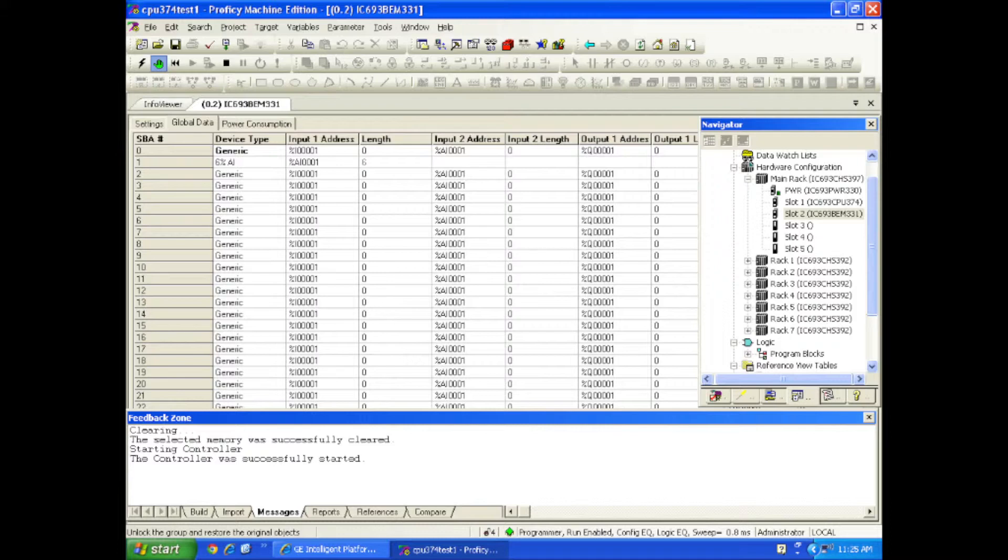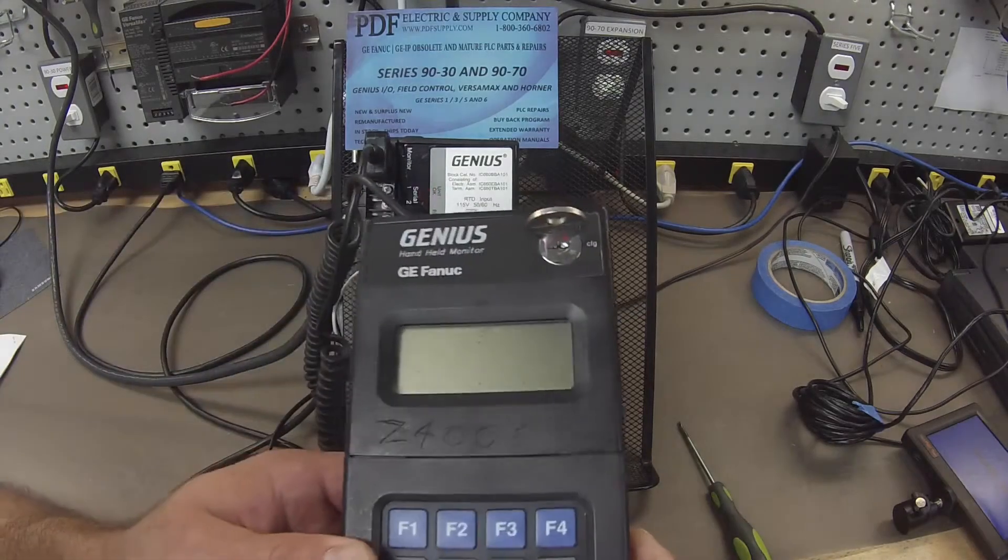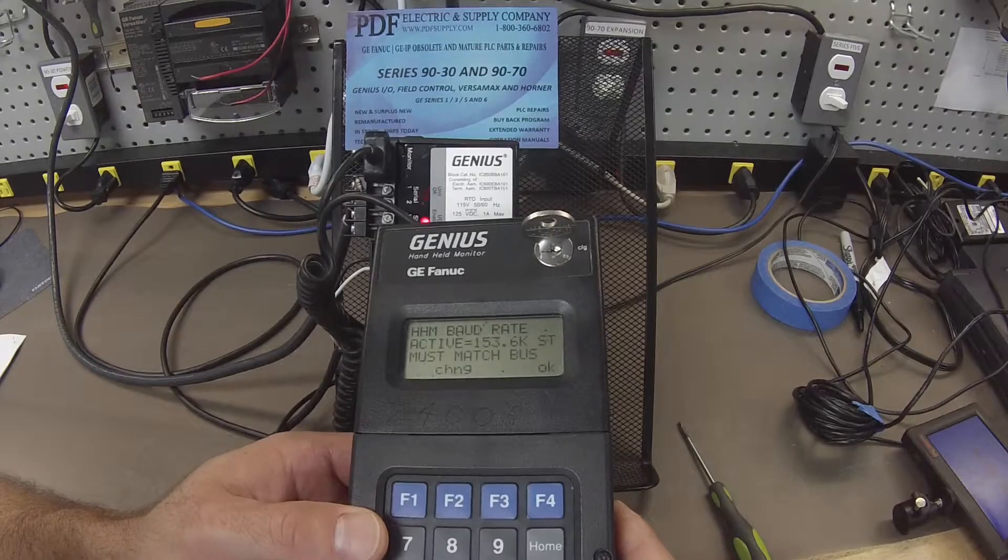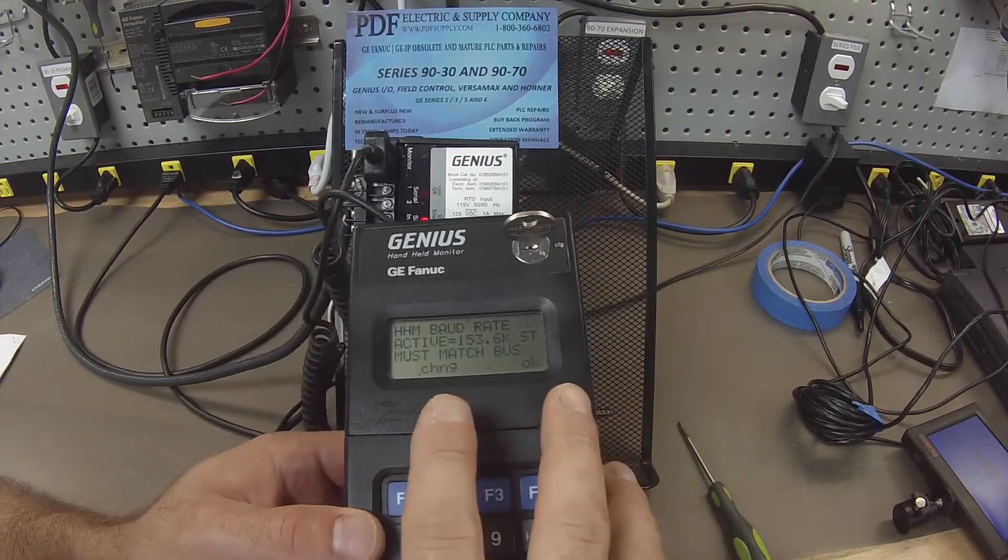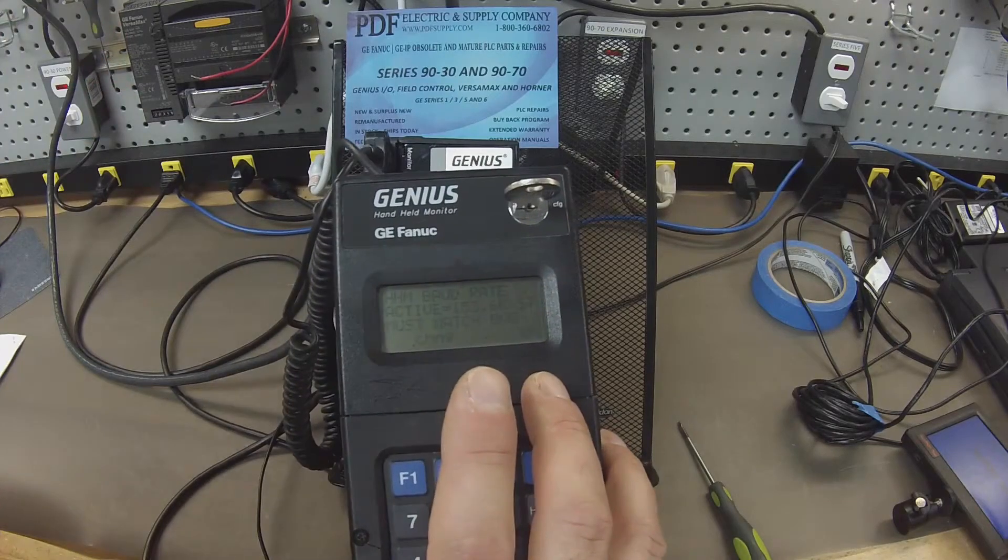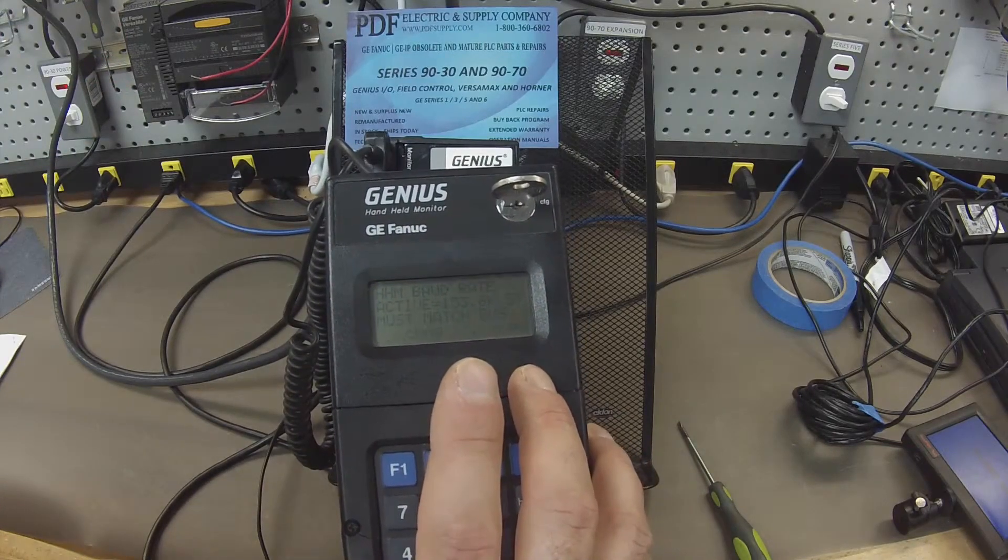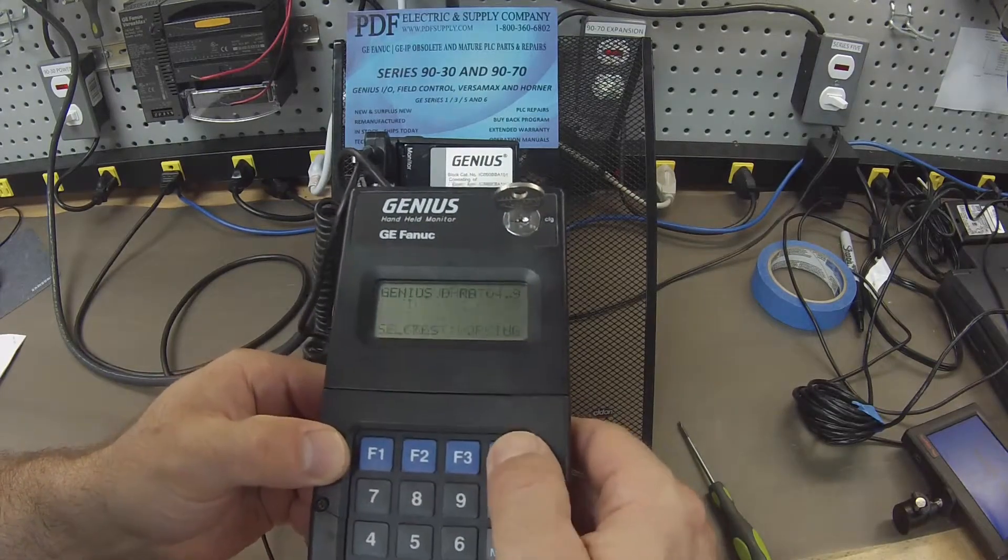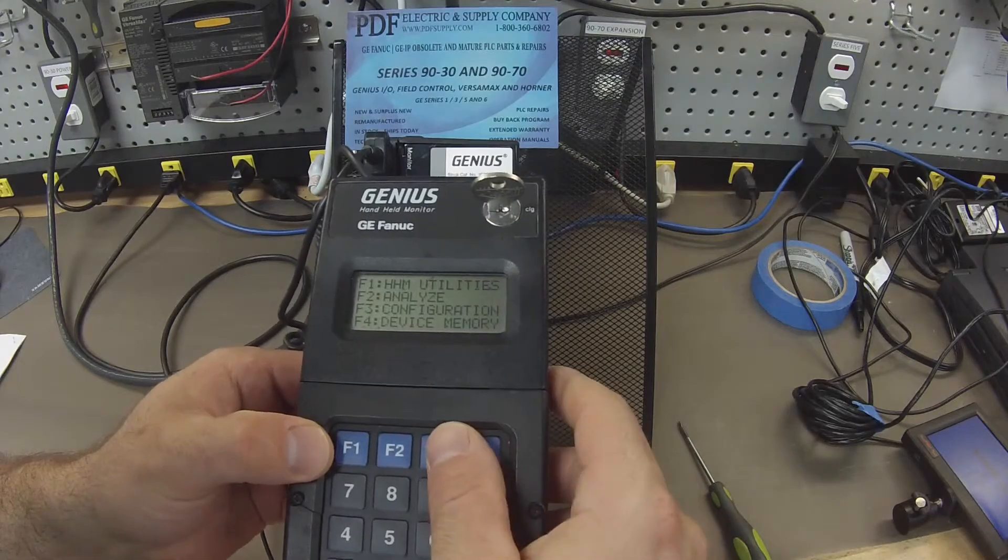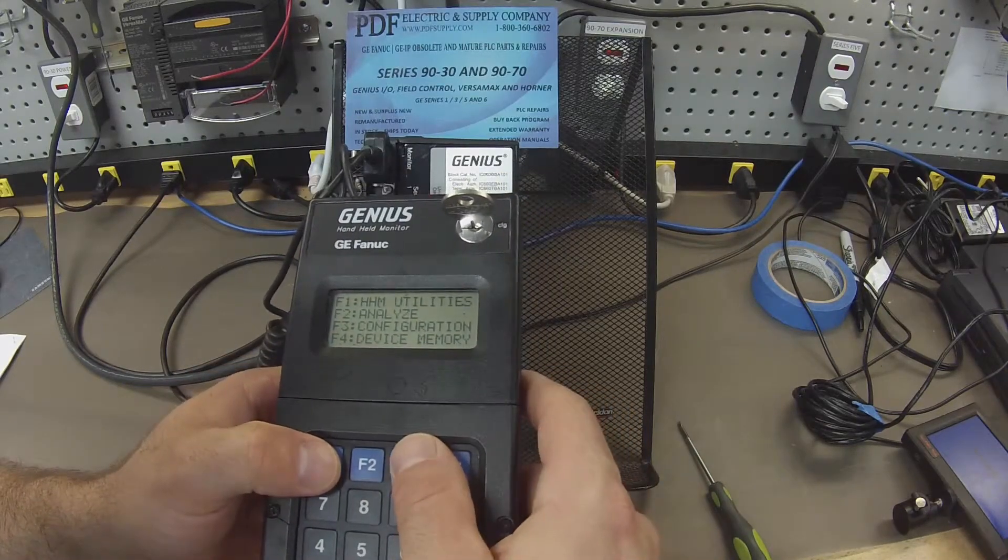So we'll start with configuring the block. Again this is the handheld monitor HHM501 and the first thing I'm going to check is that for my purpose I use the factory settings on the block, the factory settings and scalings for the block. So for those of you out there I wouldn't recommend changing any of your settings if this is a working block. This is just what I do for a test so I'm going to click OK because I know it's communicating at 153.6K standard baud rate.